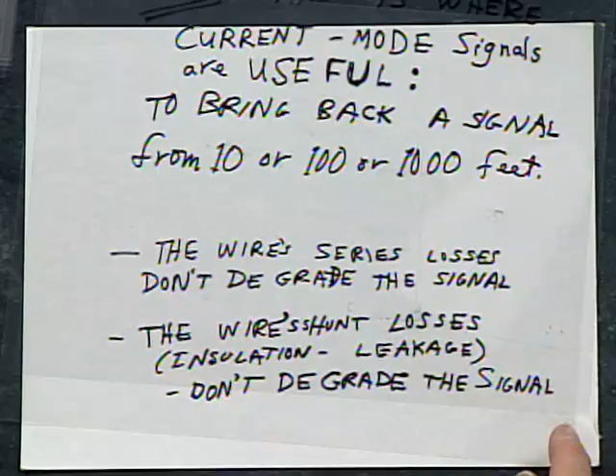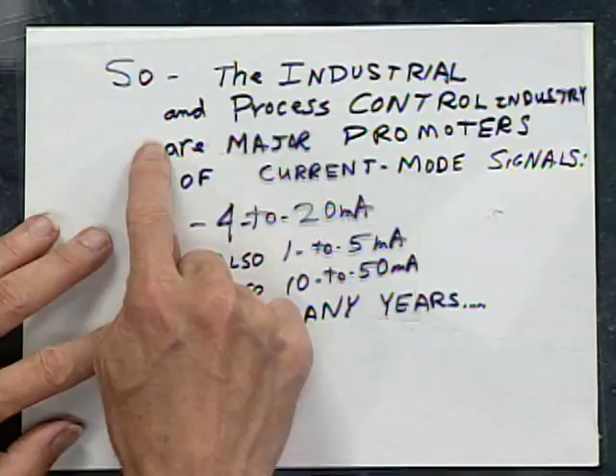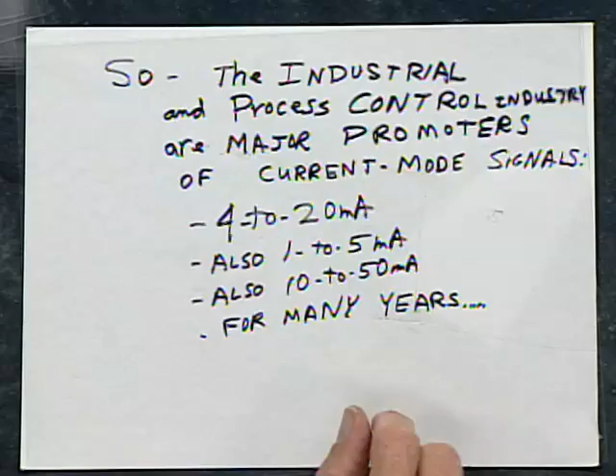And the wire's shunt losses do not degrade the signal either. The insulation is damn good, and the series resistance is finite - we don't care. So when the signal gets back, it's a current; you shove a current into a resistor and people can get full accuracy. So industrial guys and process control guys like current mode signals - 4 to 20 milliamperes, 1 to 5 milliamperes, 10 to 50 milliamperes - and they've been doing it for a long time.